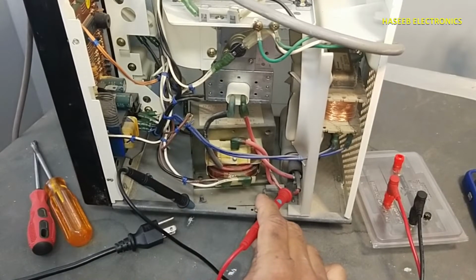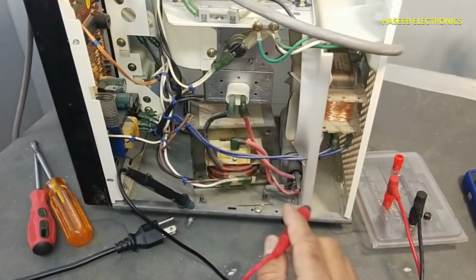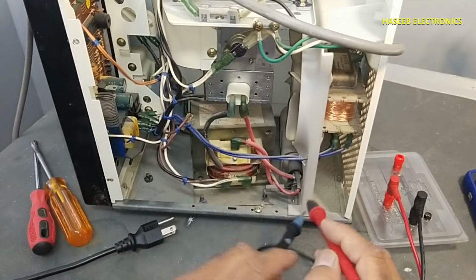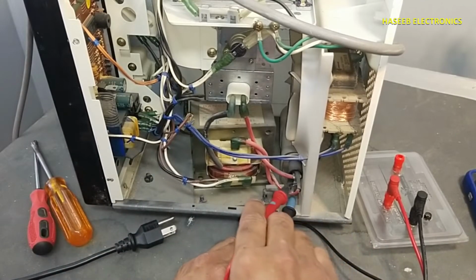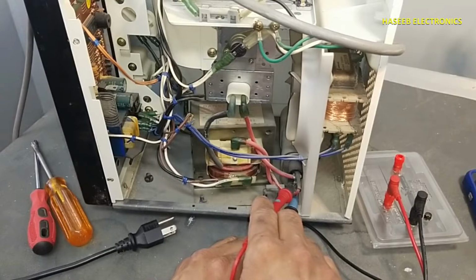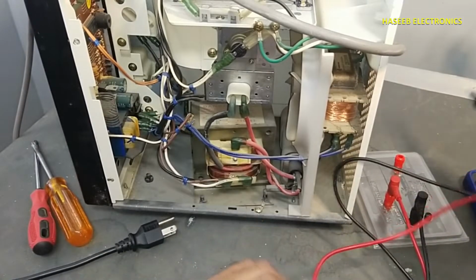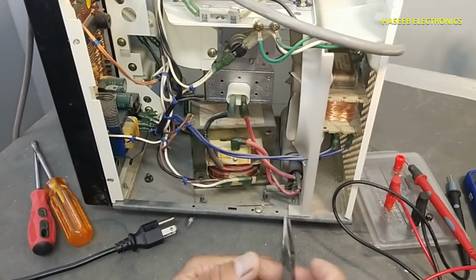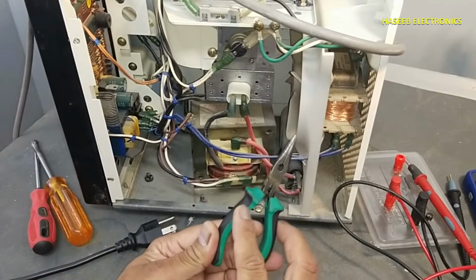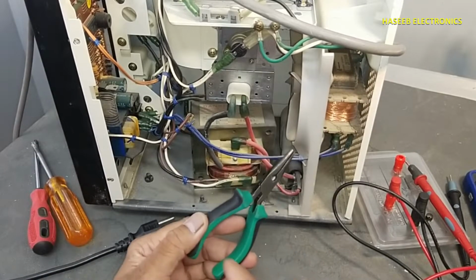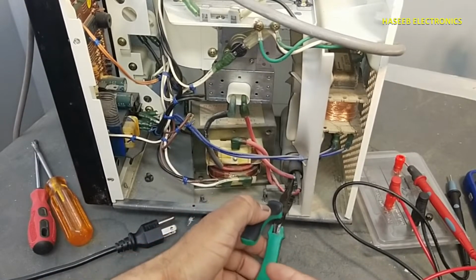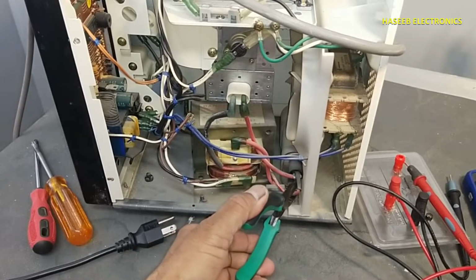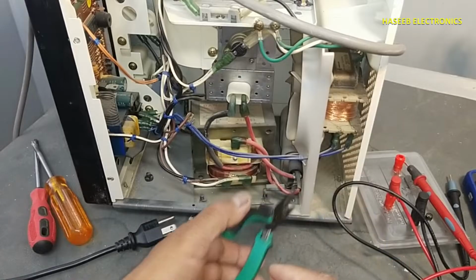Connect to the capacitor's second end. Both terminals must be discharged one by one, and for more safety, connect between both terminals. For an extra layer of safety, use long nose pliers with good insulation on the grip. Connect between both terminals of the capacitor. Discharge it.